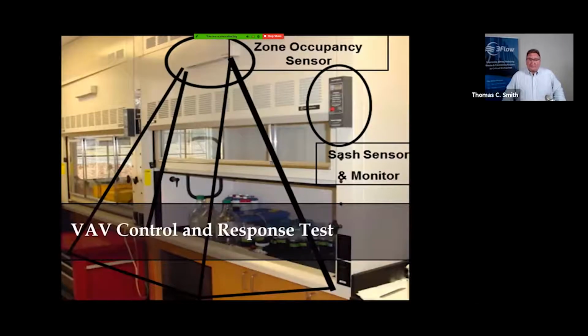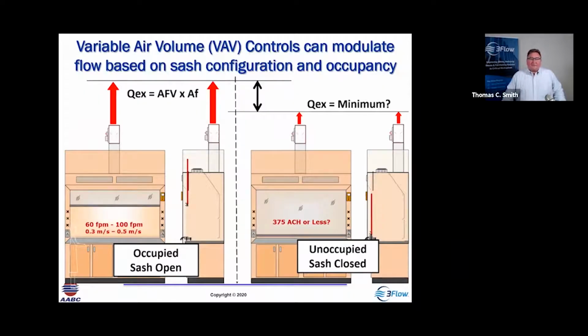So VAV controls come in lots of different types of equipment and different configurations. We have sash sensing, through the wall velocity sensing, occupancy sensing, and combinations of these different components. That makes systems very complicated, with a lot of different potential modes of operation that need to be challenged and confirmed that they work properly. The VAV system is relied upon to modulate flow from sash open to sash closed. In the sash open position, we need to know the minimum flow required. And when the sash is closed, how low can we go? What's that minimum? How do we determine that we're at the appropriate minimum flow?